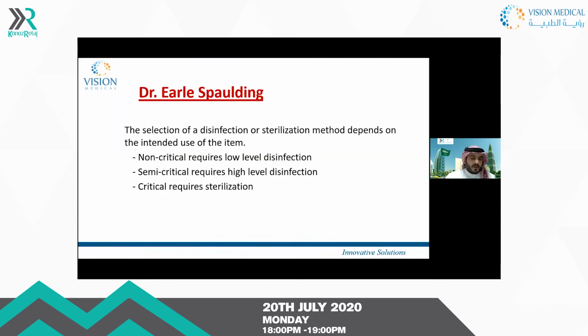So we have this old saying from Dr. Earle Spaulding: the selection of the disinfection methods, even sterilization, is based on the instruments themselves, the category of the instruments, either non-critical, semi-critical, or critical. Non-critical items need low level disinfection, semi-critical need high level disinfection, and critical items need sterilization, and sometimes high level disinfection.